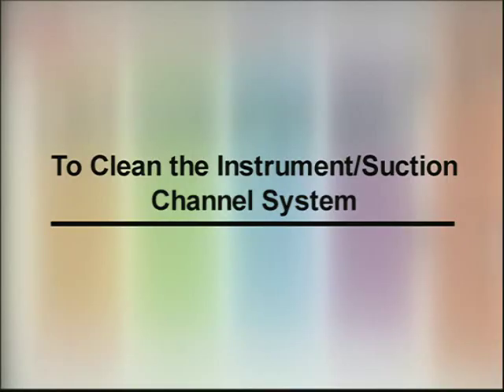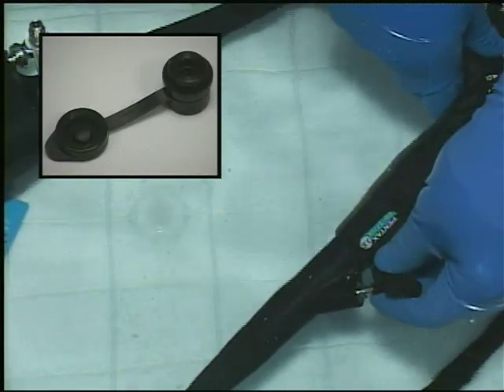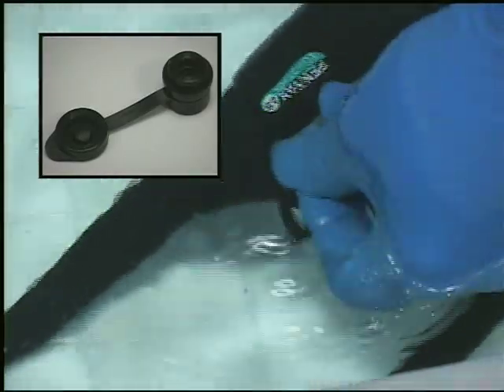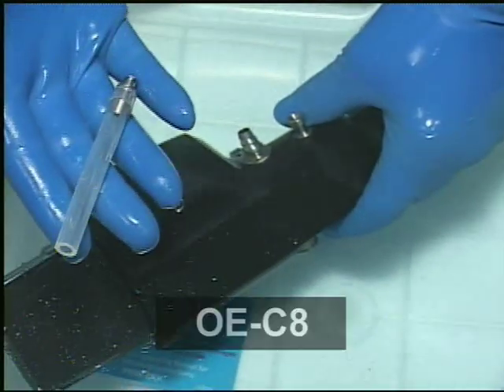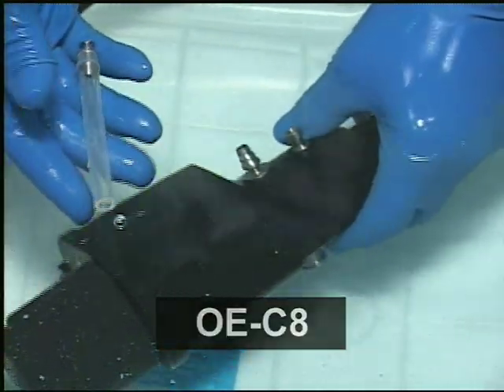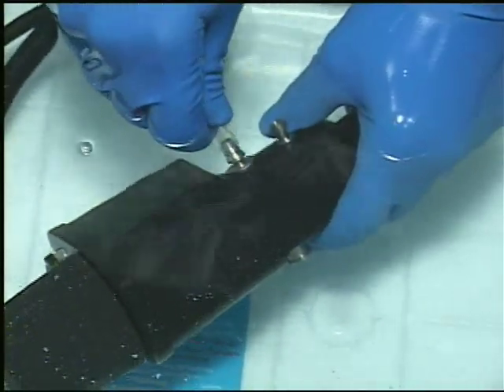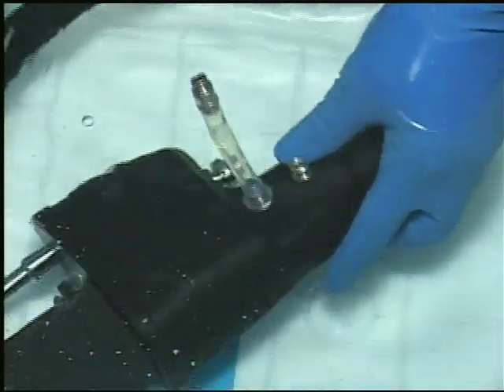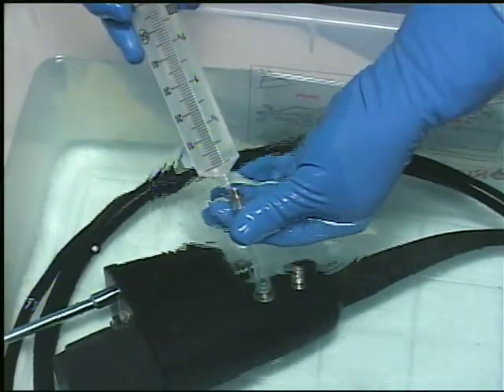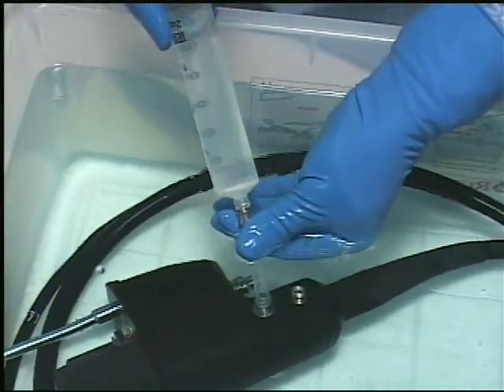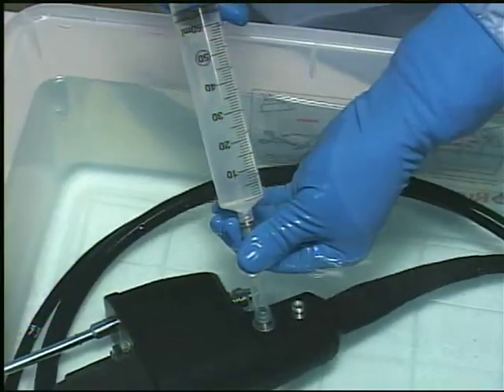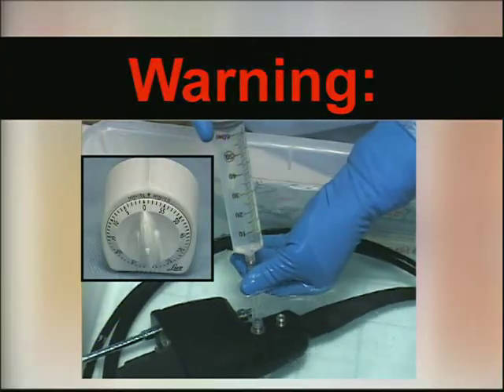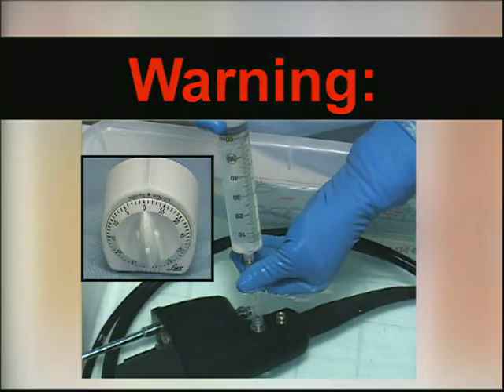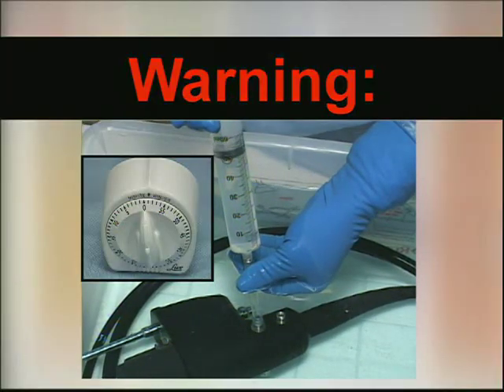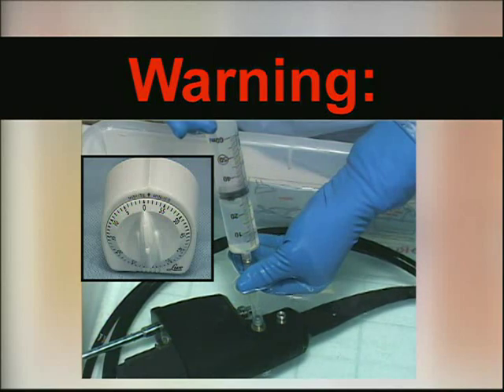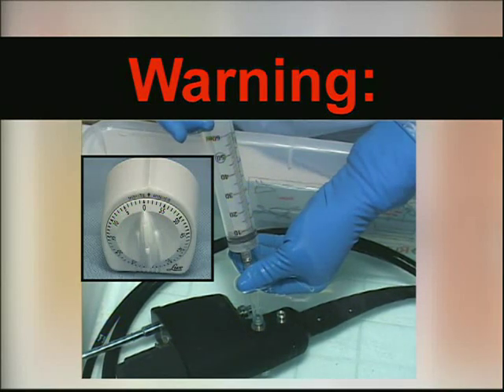To clean the instrument suction channel system, install a rubber inlet seal on the instrument channel inlet. Attach the suction channel cleaning adapter OEC8 to the suction nipple located on the PVE connector. Attach a syringe to the cleaning adapter and flush fresh detergent solution through the entire instrument suction channel. Warning: the enzymatic detergent solution should remain in contact with all internal channels and external scope surfaces for the time period recommended by the manufacturer of the detergent.